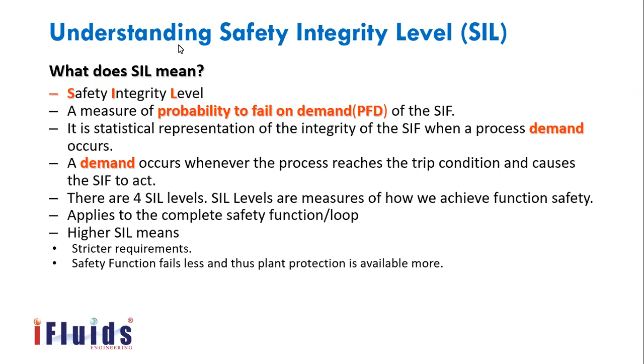What is a SIF? You can see a sensor. This is what we used to call the initiating element. From it the signal goes to a logic solver, and the logic solver trips it. So any pressure increase or anything on the other side, it trips it. It functions automatically; there is no human dependency. There are 3 parts: sensors, logic solver, and final element. Together this is what we call one SIF, safety instrumented function.